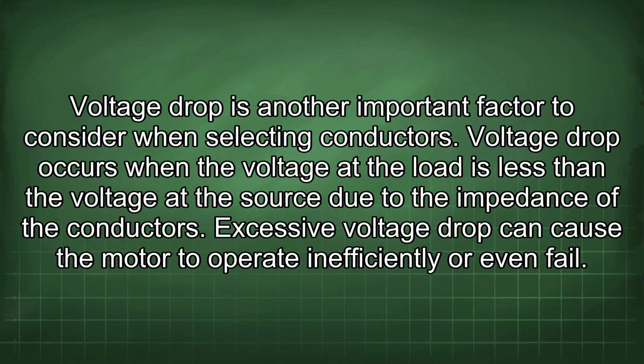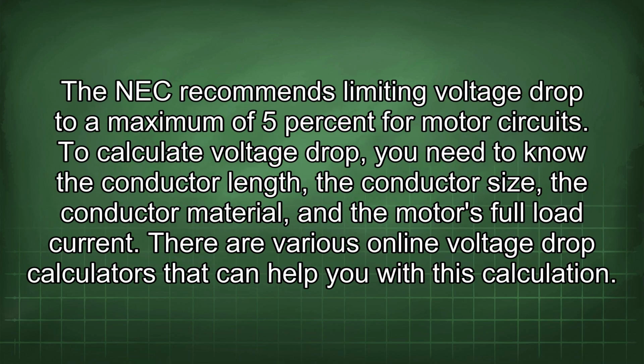Voltage drop is another important factor to consider when selecting conductors. Voltage drop occurs when the voltage at the load is less than the voltage at the source due to the impedance of the conductors. Excessive voltage drop can cause the motor to operate inefficiently or even fail. The NEC recommends limiting voltage drop to a maximum of 5% for motor circuits.